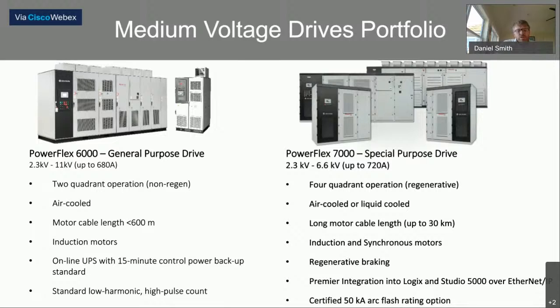It is a 2-quadrant drive, so it doesn't have the ability to do any kind of regen. It's mainly for induction motors only. Can run cable lengths up to about 2,000 feet. Its design inherently makes it low harmonics. It's also, in the medium voltage drive world, the smallest footprint of any of the other drives. And it has a rating from 2,300 volts all the way up to 11 kV, and you can get up to 680 amps.